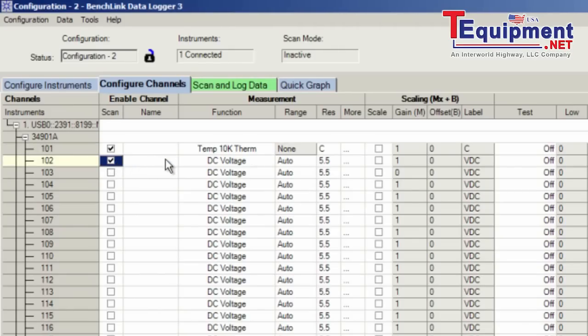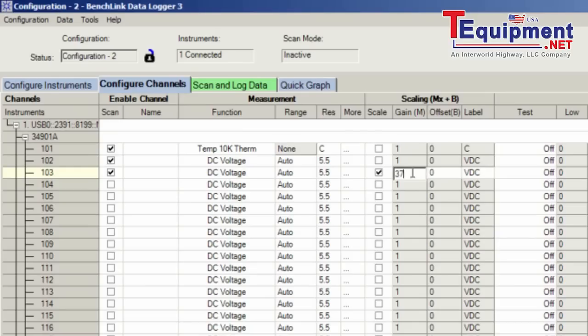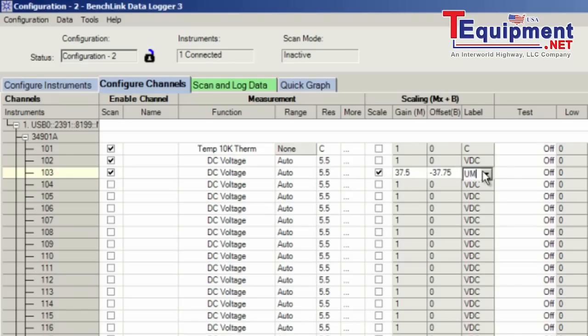My next channel is just a straight DC voltage, so I'm going to go ahead and keep the defaults. My third channel is also a DC voltage, but I'm going to scale this channel. I can enter a scale value of 37.5 and an offset of minus 37.75. Since I'm no longer measuring a straight DC volts, I can also change my label to be something that makes more sense to my measurement. I've gone ahead and made that change.